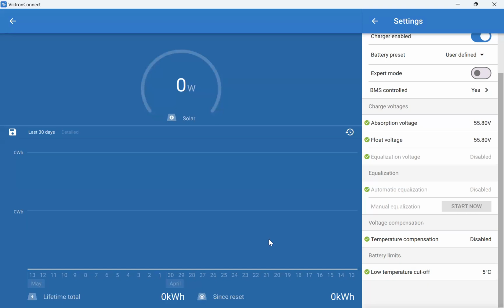What you should also see is that temperature compensation is disabled. Temperature compensation is generally for lead acid batteries and a few other chemistries, but not lithium. Low temperature cutoff is set at 5 degrees. You cannot charge a lithium battery below 0 degrees, otherwise you'll damage it, so 5 degrees is just a safety threshold.